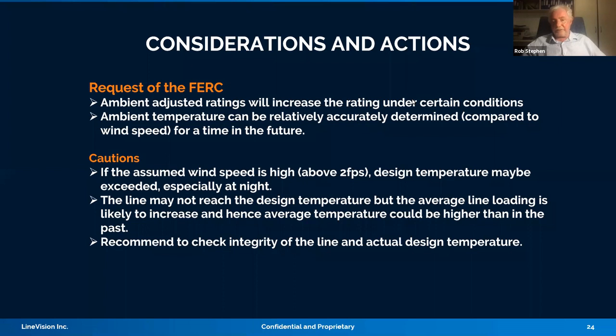I think that's all really what I want to highlight, Alex, and I'll take any questions on this. We can, of course, go into any details on the different types of probabilistic and deterministic ratings, as well as many kinds of dynamic ratings and real-time monitoring. But in conclusion, I think what's happening here is the correct thing to do. And there are many ways you can upgrade the thermal rating of the line. What we're looking at here is monitoring systems and calculations, which will do that. Of course, you can increase your design temperatures by increasing the height of the conductor above the ground by retensioning and so on, which will also increase your thermal rating of the line.